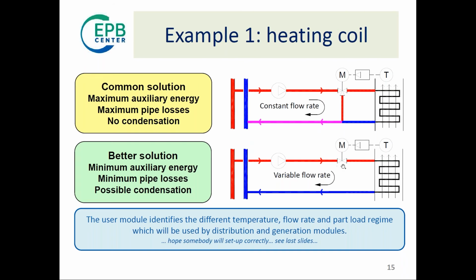It could be much wiser to use a two-way valve and profit from the reduced flow rate, which means reduced auxiliary energy and reduced temperature on the return line. So in the common solution, you have maximum auxiliary energy, maximum heat losses from the pipe, and no condensation if you are connected to a condensing boiler. This is a better solution: minimum auxiliary energy, profiting from electronic pumps, minimum heat losses, and possible condensation.